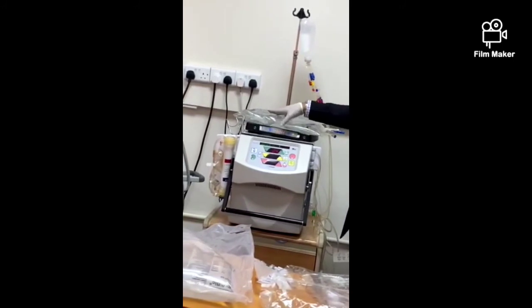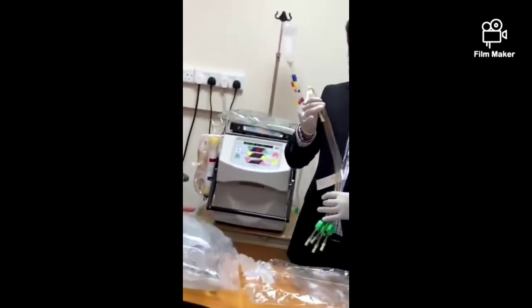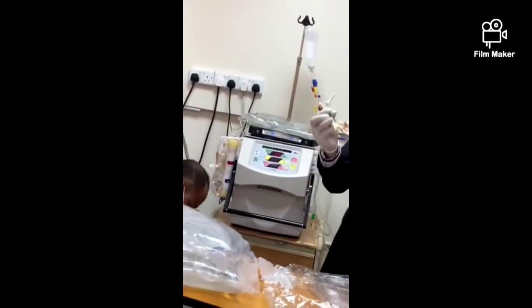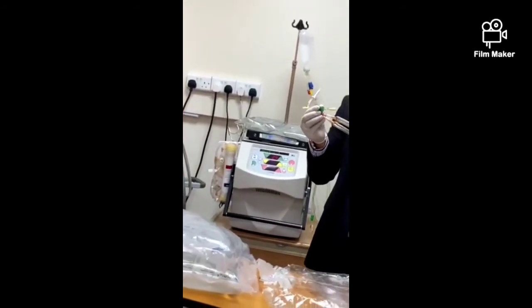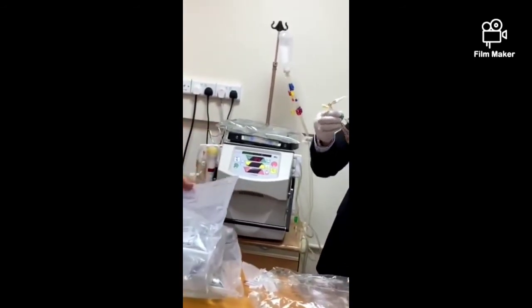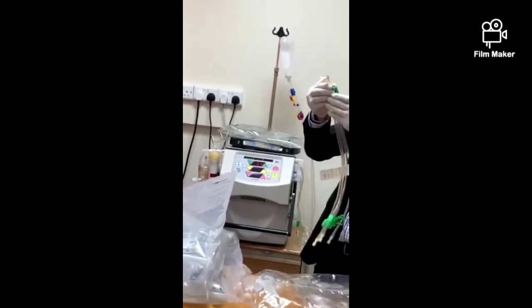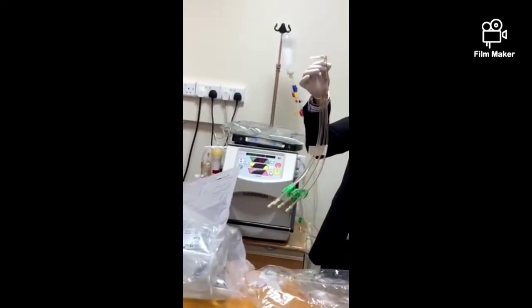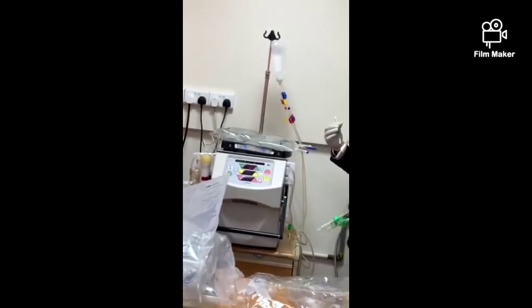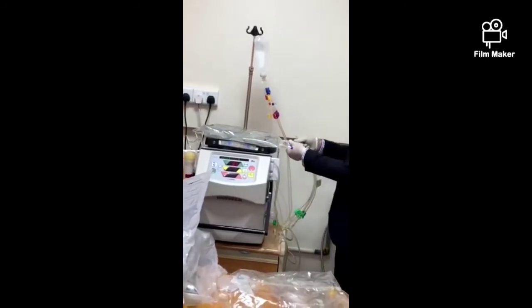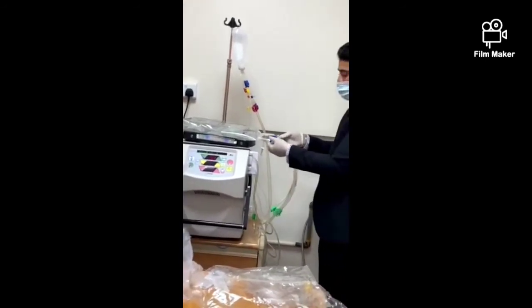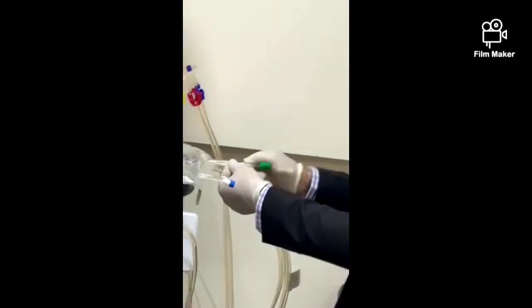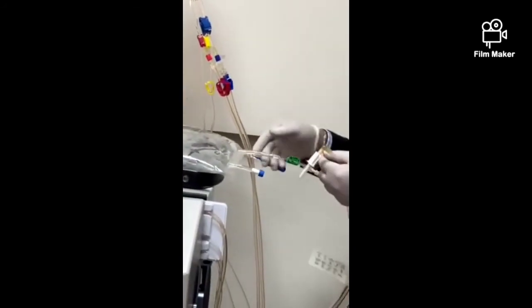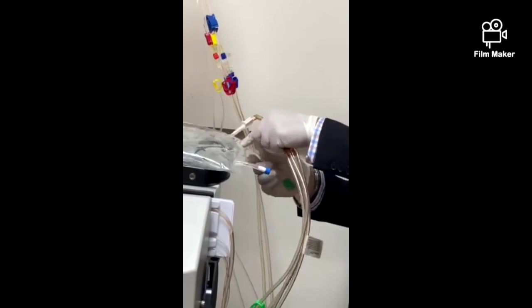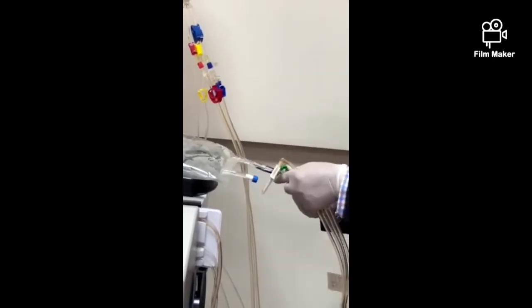After you put the dialysate, don't forget to set the temperature. Then the next thing, the fourth item, is this one, the green. This is the warmer line or dialysate line. When you open the warmer lines, you see there is one small and one big. Where will you connect the small one? You see here, the warmer. Just connect here, one side, small, like that. And before you forget, just break it. It is already broken. No, we need to break it.